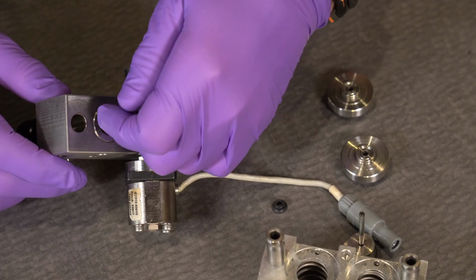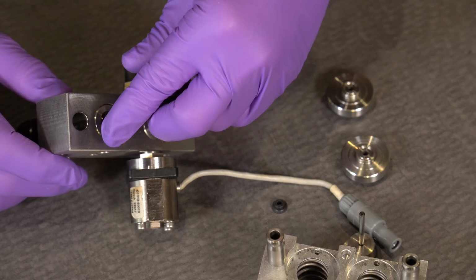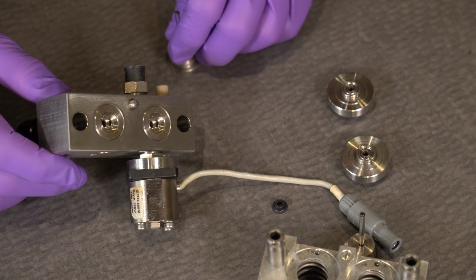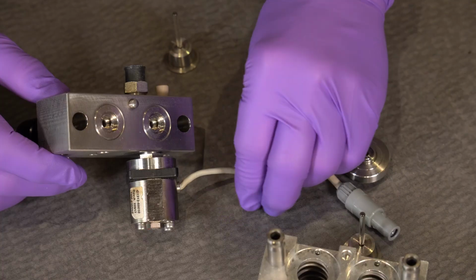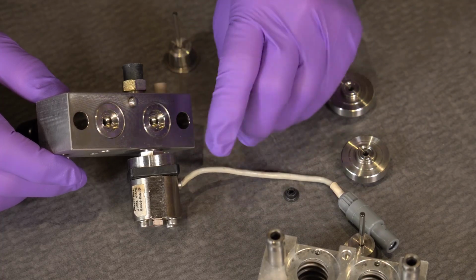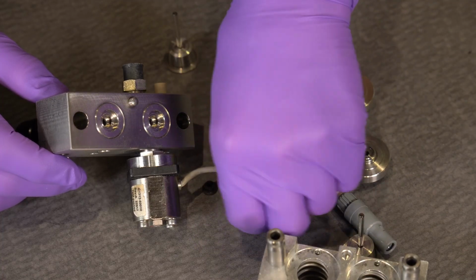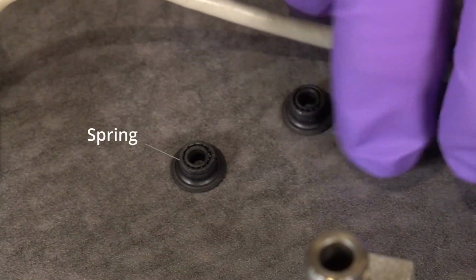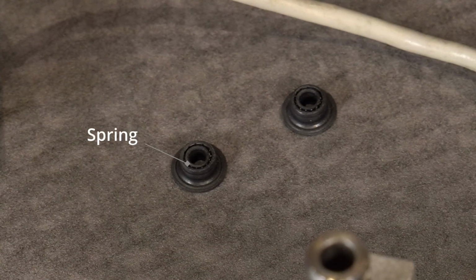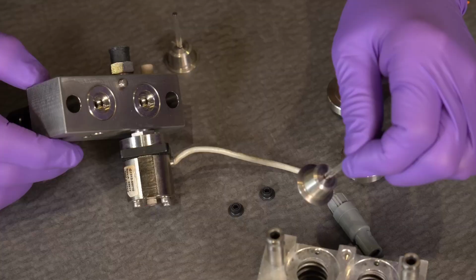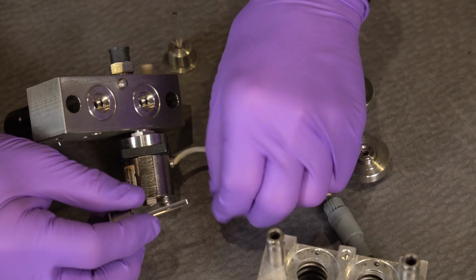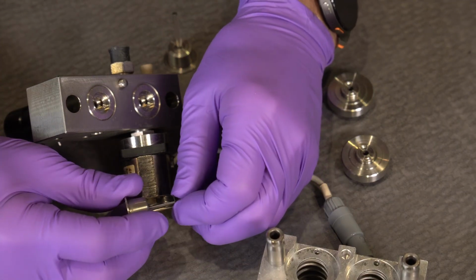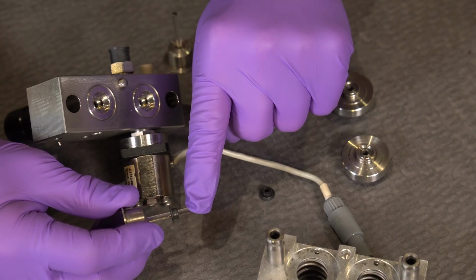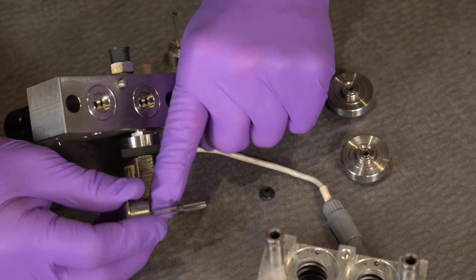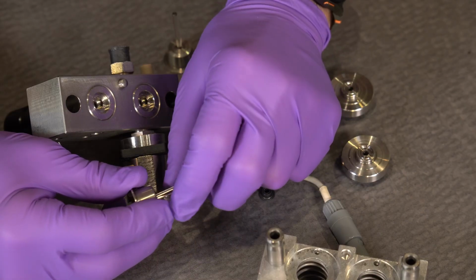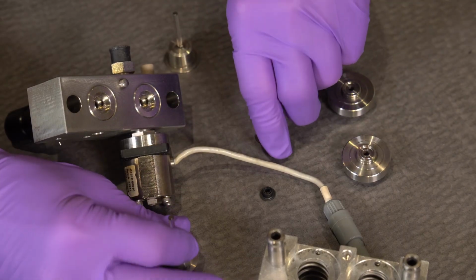So you always change both pump seals. Never go through all this hassle just to change one. So we change both pump seals. Those are the old pump seals. If you look at them very carefully, sometimes you could see there's a little spring on the inside, and the spring actually helps it grip onto the piston itself. So the piston and the piston seal internally are going to fit together like this. On one side, we're going to have 9,000 psi, and the other side, we're going to have 0 psi. So you get the idea of how important that pump seal is. So when it wears out, we're going to replace them.